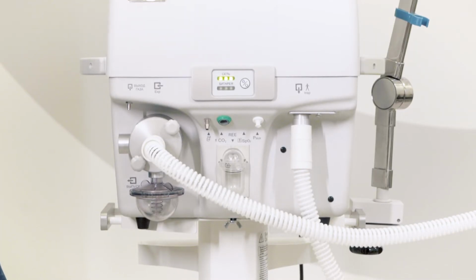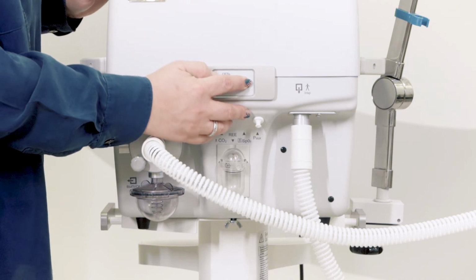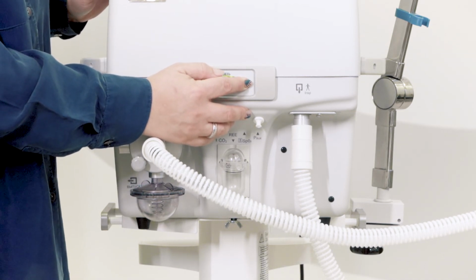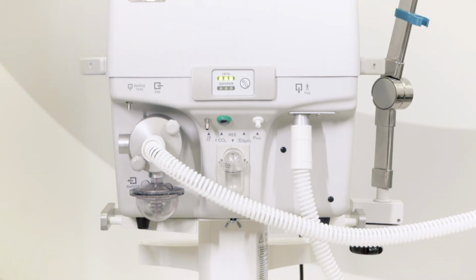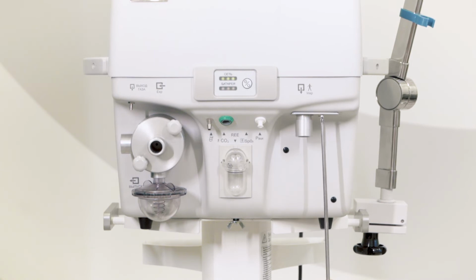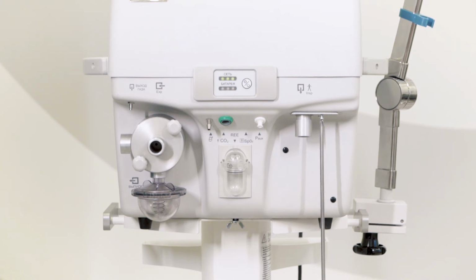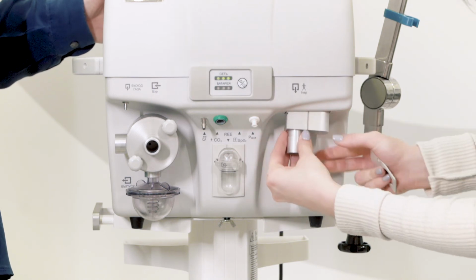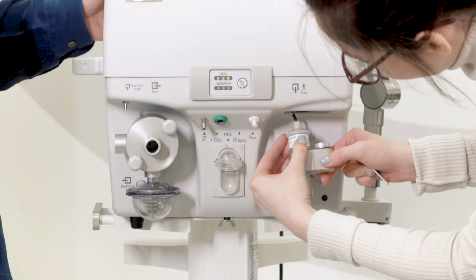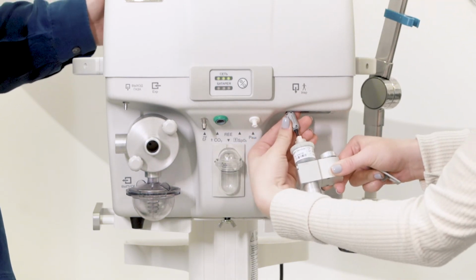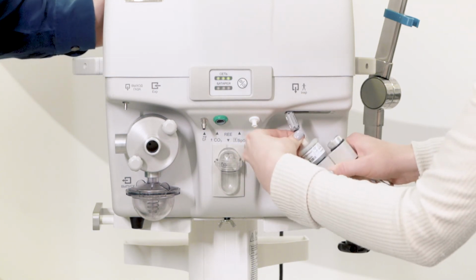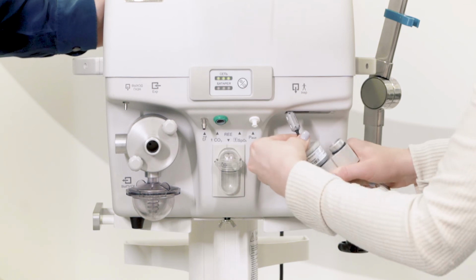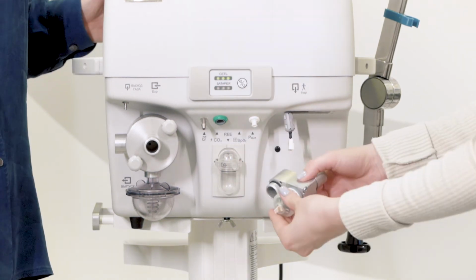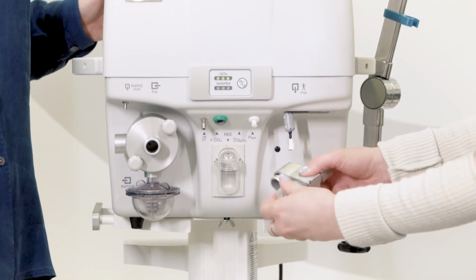FiO2 sensor replacement. For the replacement of the FiO2 oxygen sensor, switch off the device. For this purpose, unscrew the 2 screws of the oxygen sensor cover. Carefully take the inspiratory connector assembly so as not to break off the wires of the connector. Disconnect the sensor power cable. By counterclockwise rotating, unscrew the faulty sensor.